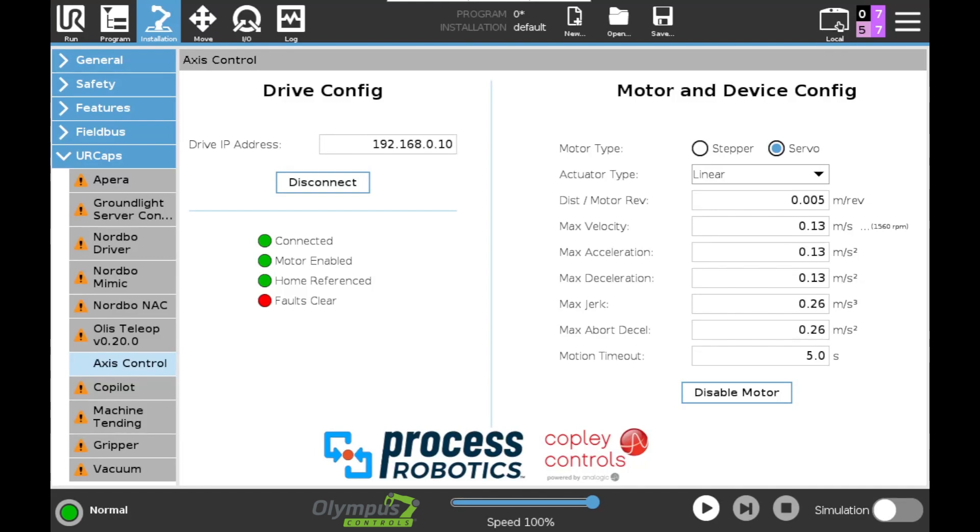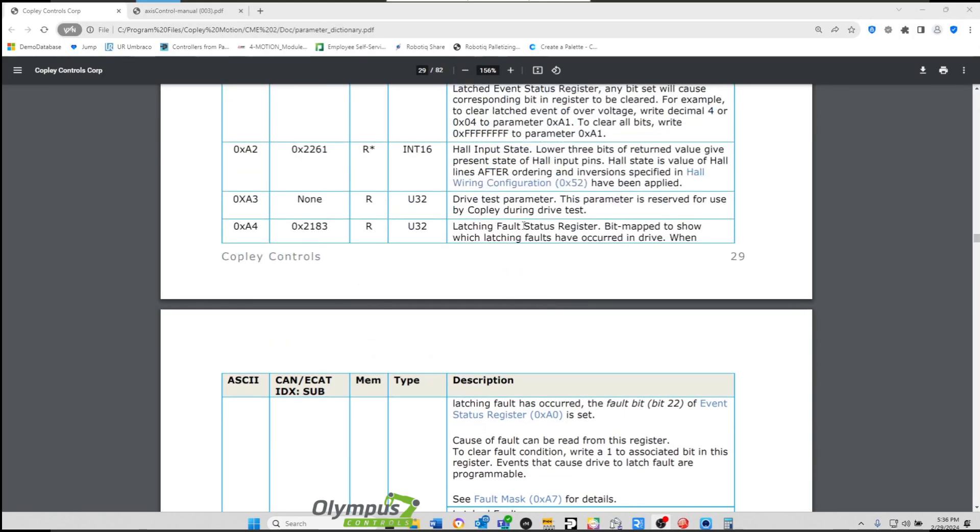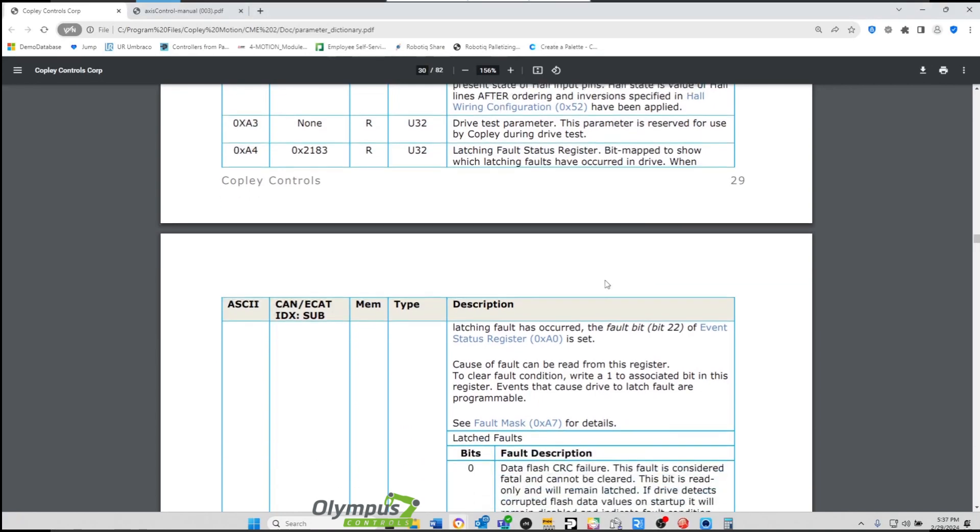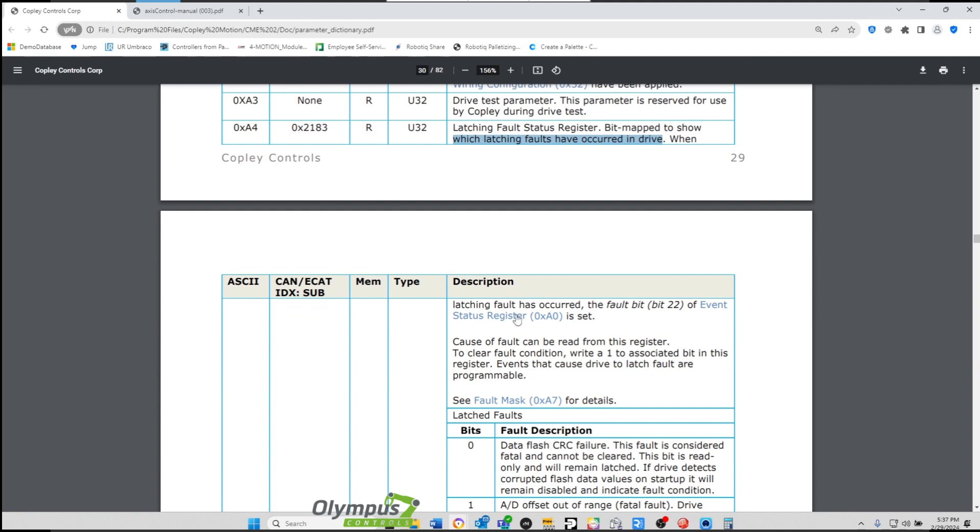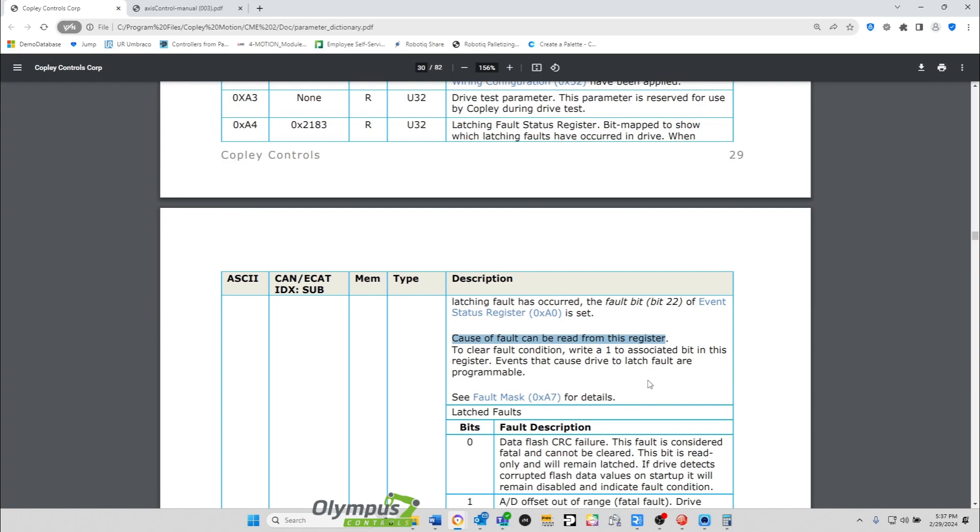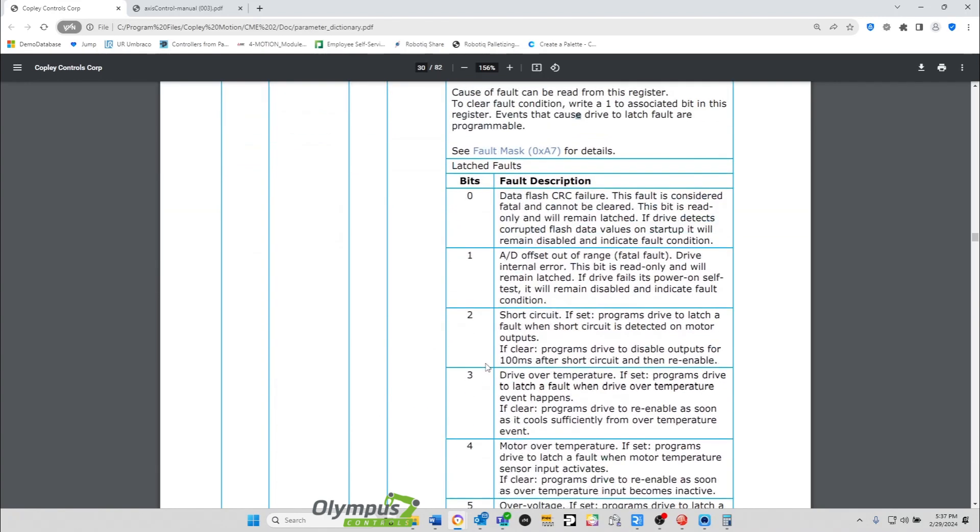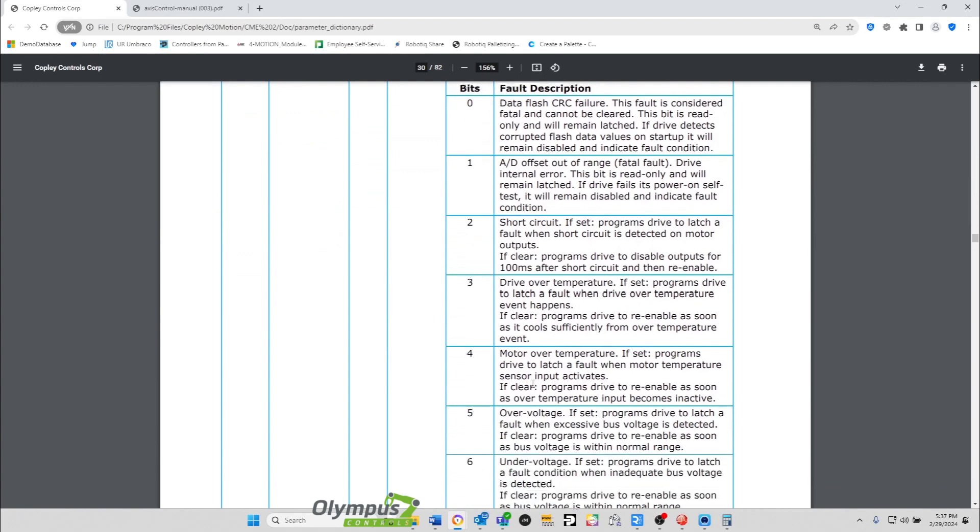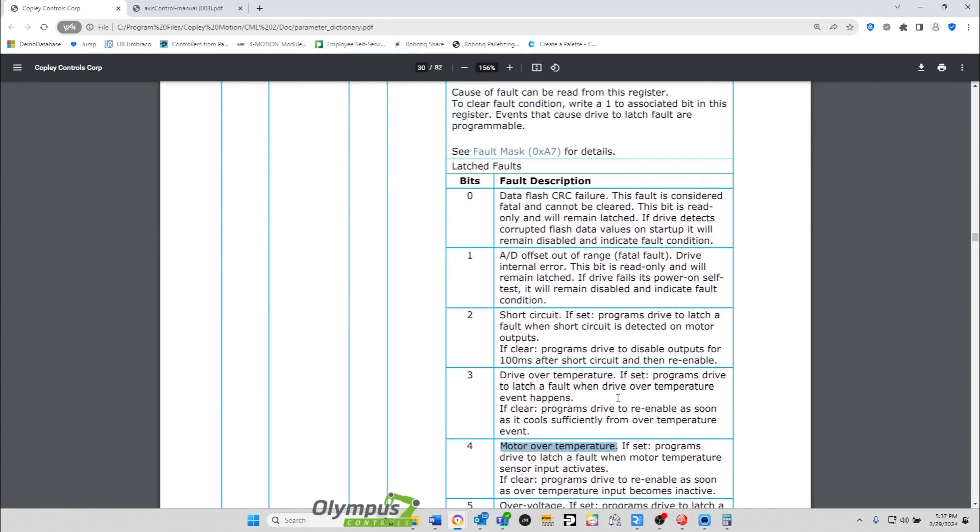And what we're going to need to do is clear these faults. Let's take a look at the parameter dictionary. Now here under the latching fault status register, you can see this is one of the registers in the parameter dictionary and it's bit mapped to show when latching faults have occurred in the drive. The cause of the fault can be read from this register. So I can read this register from the program using one of the read parameter functions or more importantly, I can write to this parameter. You can see here to clear fault condition, write a one to the associated bit in this latching fault status register. And I know I triggered a motor over temperature error.